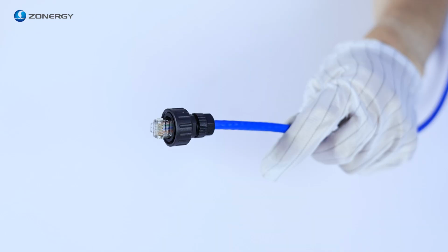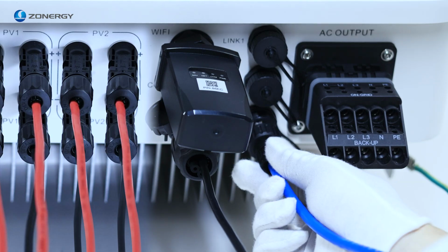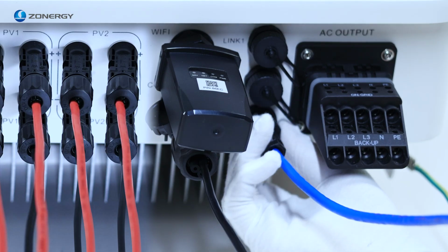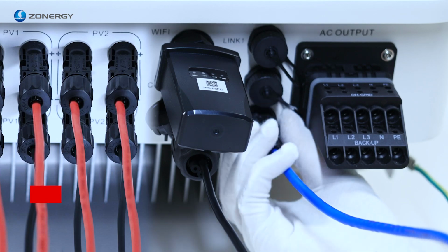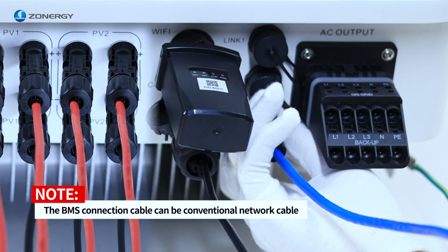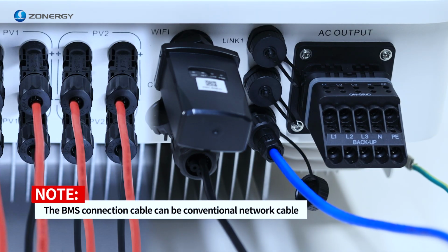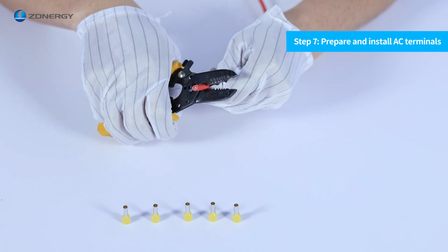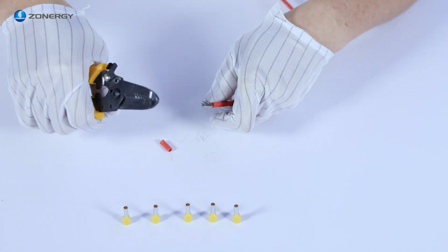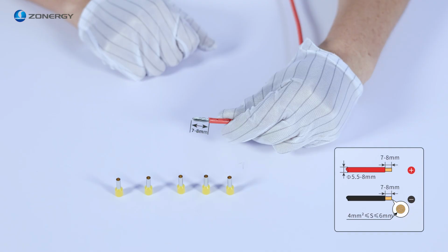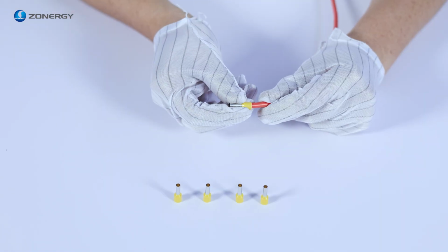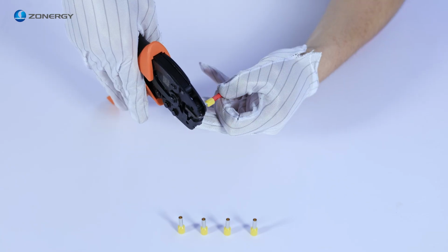2. The following is the completed BMS communication line. 3. Connect the BMS communication terminal to the inverter BMS port. Note, the BMS connection cable can be a conventional network cable. Step 7. Prepare and install AC terminals. 1. Make cable joints of appropriate length according to the mark. 2. The following is a finished AC terminal cable connector.